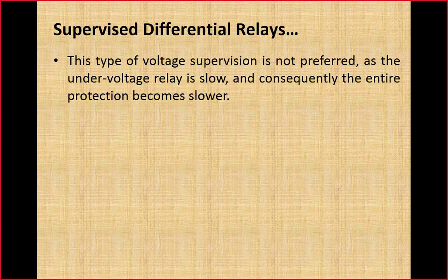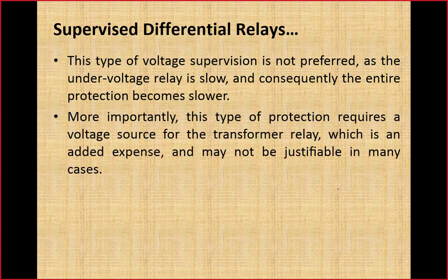Although we can provide this supervision, it is not preferred in the case of more expensive and critical power transformers that may get damaged due to the slow operation of the differential protection. Most importantly, this type of protection requires a voltage source. It means we will have to install a voltage transformer to get a voltage signal. Voltage transformers are very expensive, so that will add extra cost for the protection. Sometimes it is not justifiable.